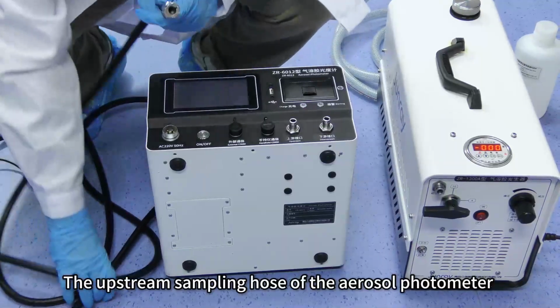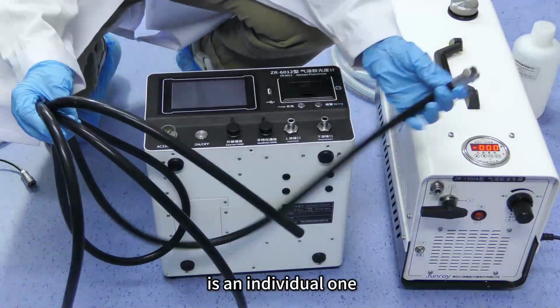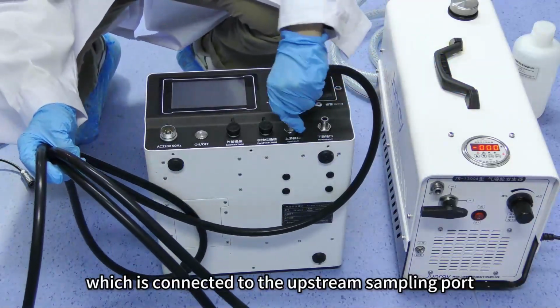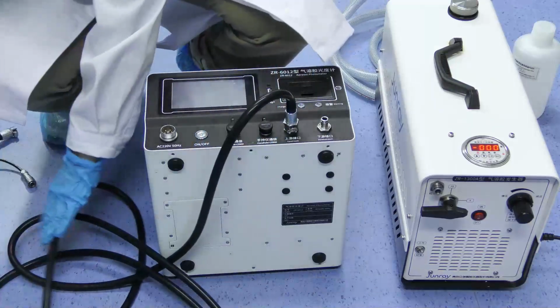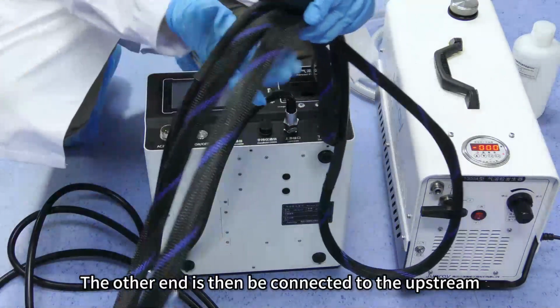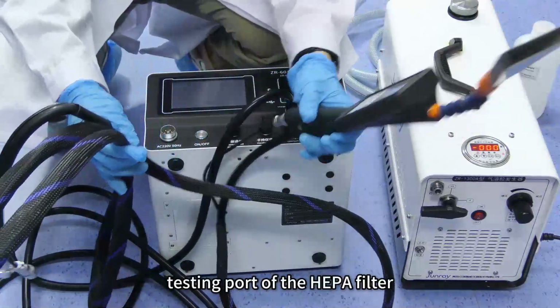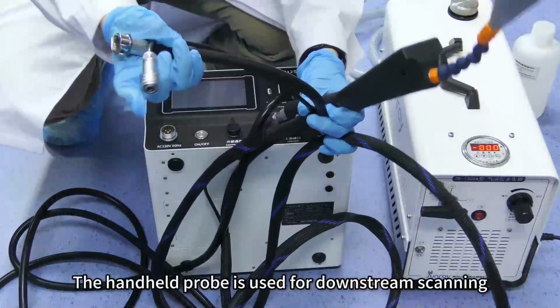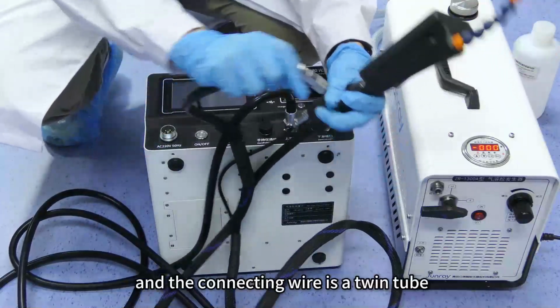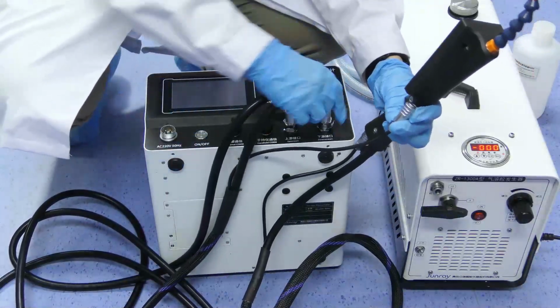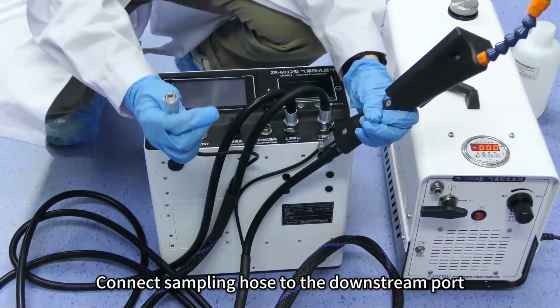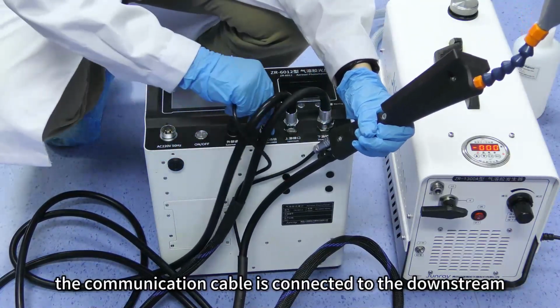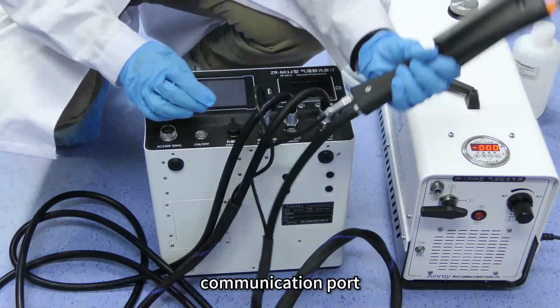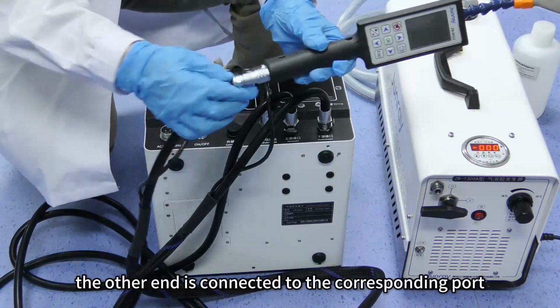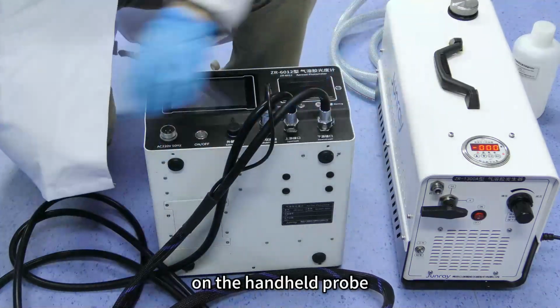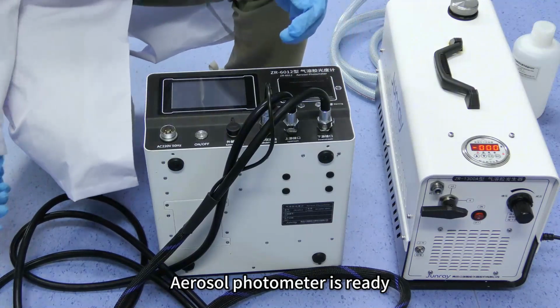The upstream sampling hose of the aerosol photometer is an individual one, which is connected to the upstream sampling port. The other end is then connected to the upstream testing port of the HEPA filter. The handheld probe is used for downstream scanning, and the connecting wire is a twin tube. Connect sampling hose to the downstream port. The communication cable is connected to the downstream communication port. The other end is connected to the corresponding port on the handheld probe. Aerosol photometer is ready.